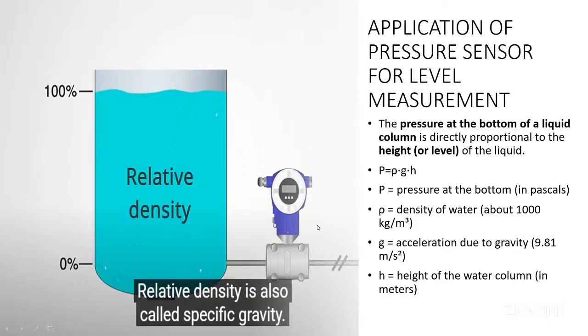If you want to make use of this in measuring level in the tank, the density or the specific gravity of the liquid itself needs to be known, that is, if the liquid is not water. For water, of course, we already have a standard value, and we already know the value for the acceleration due to gravity, 9.8. Then the height of the tank has to be determined by measuring it. You can physically measure the height of the tank, and that is what we commonly do by scaling. In the program part of it, we say we scale the sensor to harmonize with the physical tank, so as to use it for level measurement.